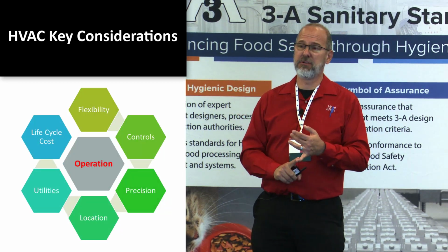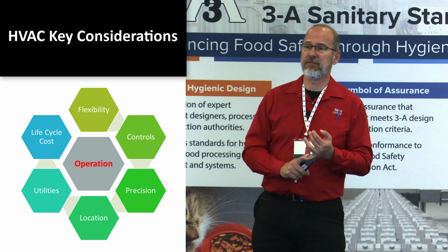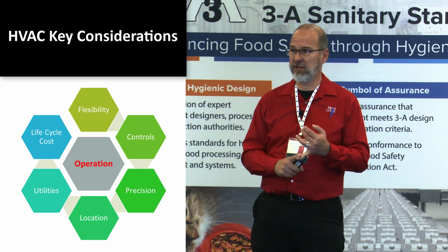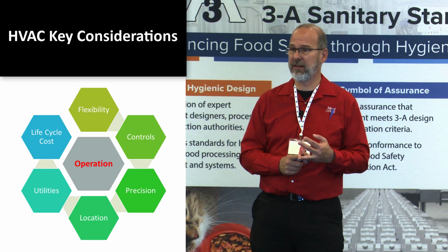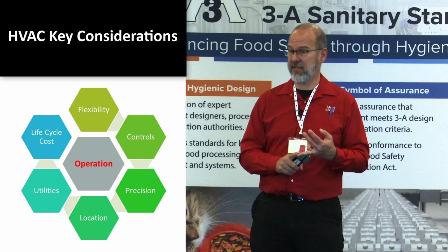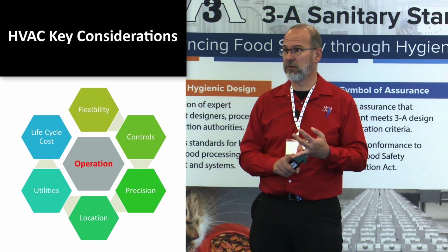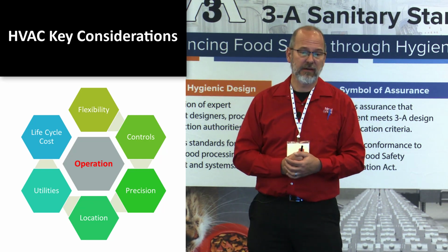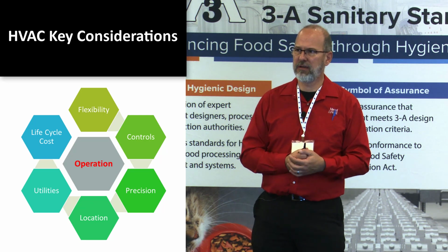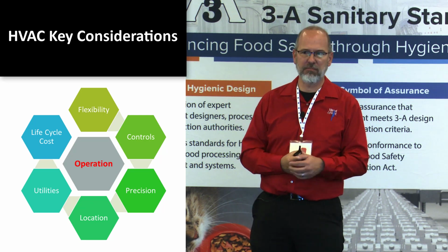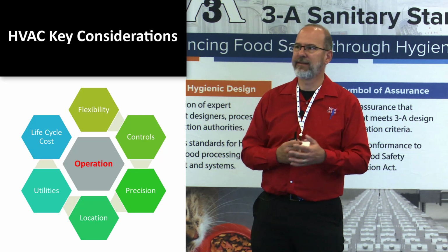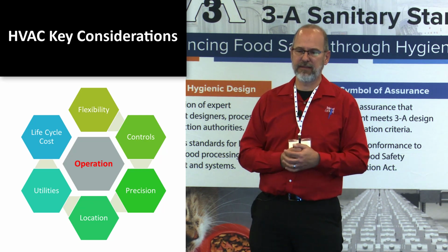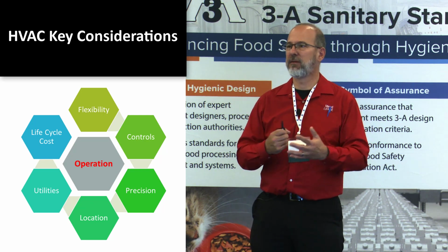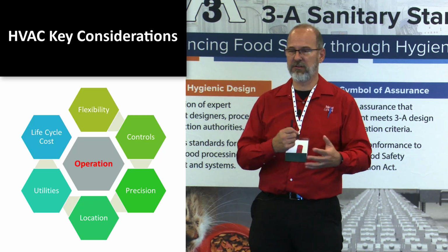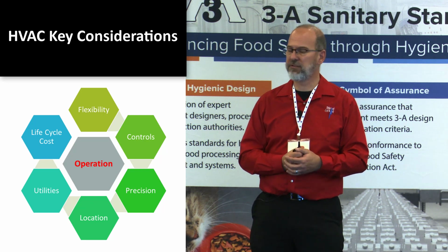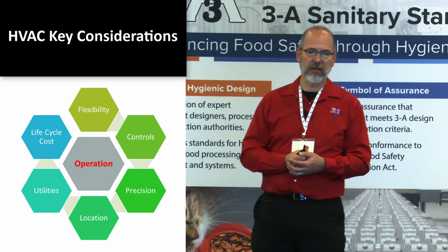You also have to consider the flexibility of the unit, how it operates. If you need to make changes on the fly, how easily can you do that? Controls are important in an air handler. Are you going to connect it to the plant PLC system or not? Or is it just going to be a standalone wall panel in the process room? What kind of precision are you looking for with this kind of HVAC unit? Do you want plus or minus a half a degree Fahrenheit and plus or minus 2% relative humidity? Obviously, you're going to pay a lot more for high precision. So that's another one of the factors that needs to be considered when you're designing HVAC systems in a food factory.